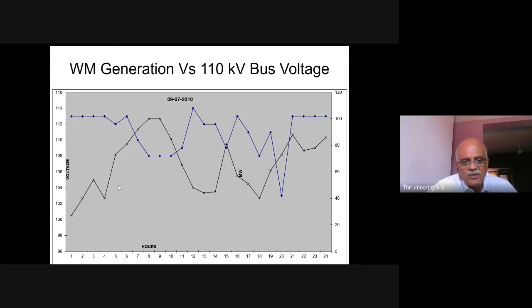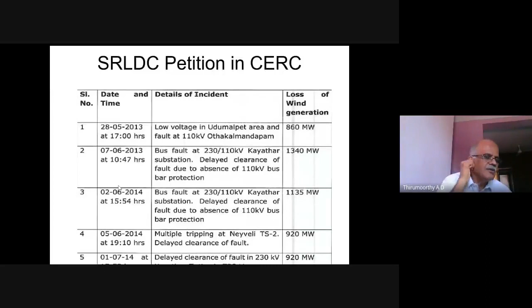After these kind of studies, they have amended the grid code to the exact requirements. This is actually the scenario in the southern region. In these dates, you can see that these amounts of windmills have tripped due to voltage sag. You can see that in one incident, nearly more than 1,000 megawatts of windmills have tripped.